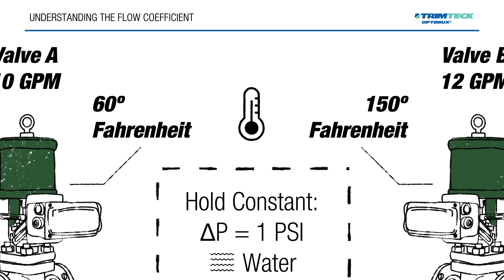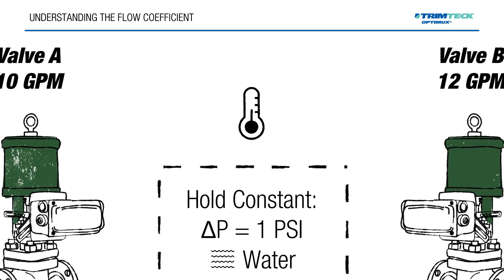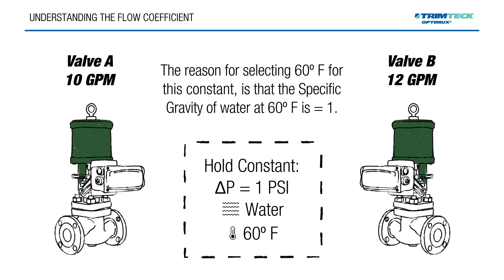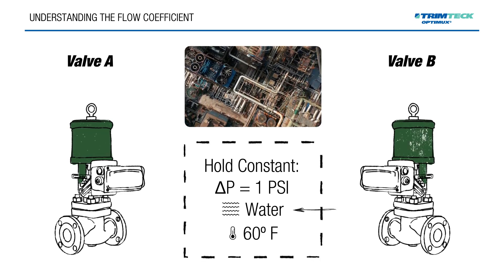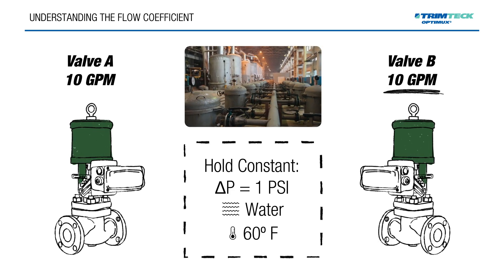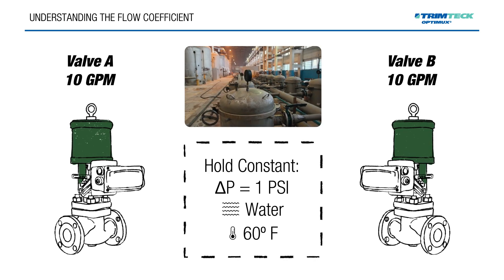Temperature also has an impact on flow — in this case, the higher the temperature of the water, the higher the flow rate. So we choose a temperature to hold constant. In all cases where CV is being measured, we select 60 degrees Fahrenheit. The reason for selecting this is that the specific gravity of water at 60 degrees Fahrenheit is 1, which makes the math much easier. Holding constant the 1 psi pressure drop, water as the fluid, and 60 degrees Fahrenheit, we take a measurement and find Valve A continuing to flow at 10 gallons per minute and Valve B now matching at 10 gallons per minute — which is the way it should be, as these are two identical valves of identical construction and trim size.